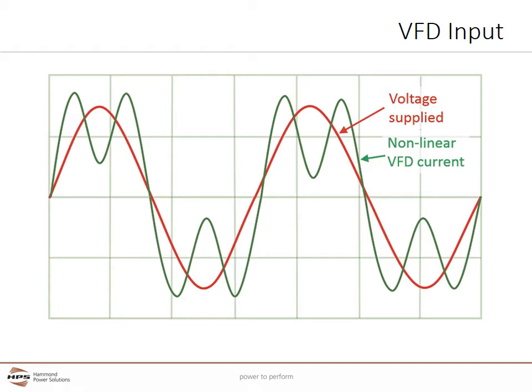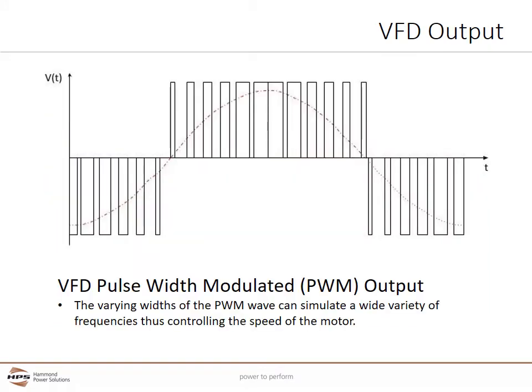The input or line side of a VFD uses rectifiers and is basically a DC power supply, creating current harmonics when it transforms AC to DC power. As a result, harmonics distort the utility's red sine wave to look like the green wave. Current harmonics can cause significant issues within the facility and if they exceed the standard called IEEE 519, the utility can fine the user. The output of a VFD uses semiconductors to quickly switch the input voltage on and off in what's called a pulse width modulated or PWM output. By varying the width of the DC pulses, a VFD can simulate a wide range of frequencies from near zero to several hundred hertz, controlling motor speed. The PWM wave can have some unintended consequences which can cause problems with cabling and the motor.